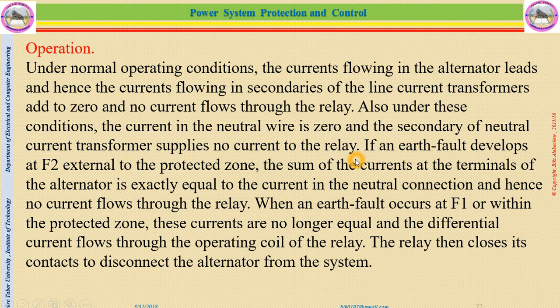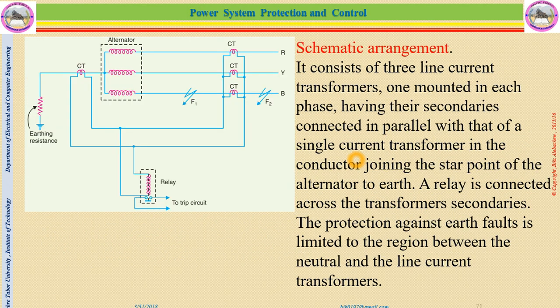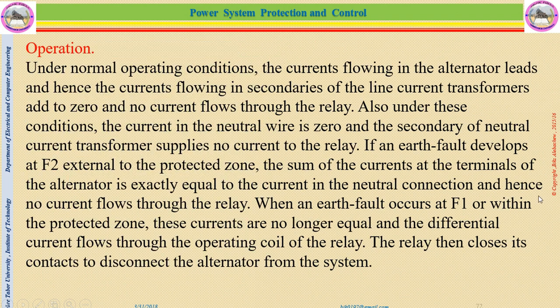If an earth fault develops at F2, external to the protective zone, you can see F2 here. If the fault happens at F2, external to the protected zone, the sum of the currents at the terminals of the alternator is exactly equal to the current in the neutral connection, and hence no current flows through the relay coil.